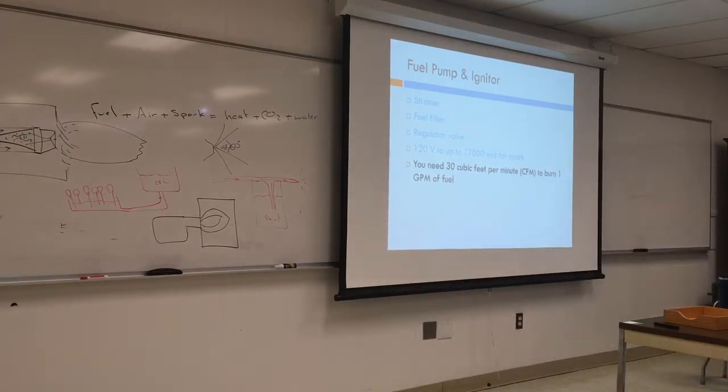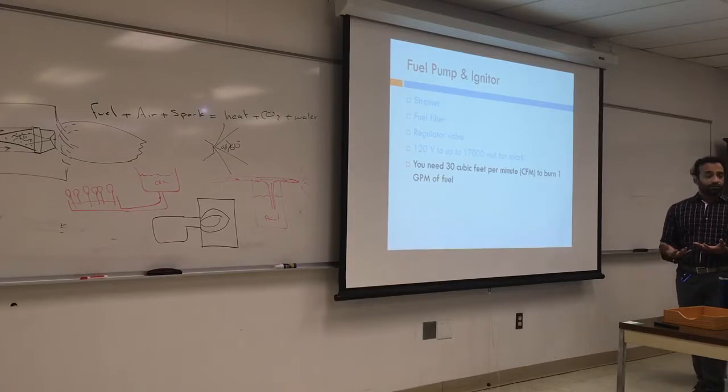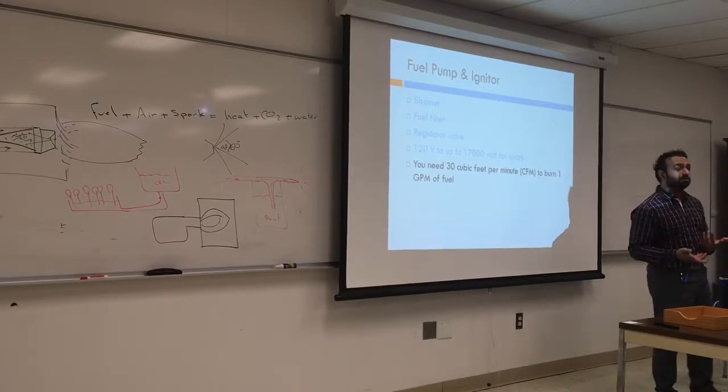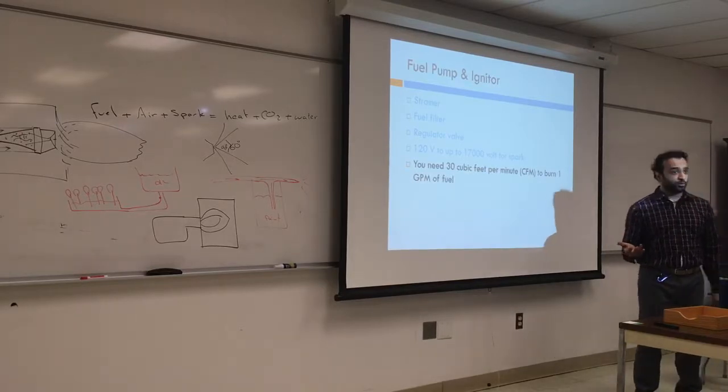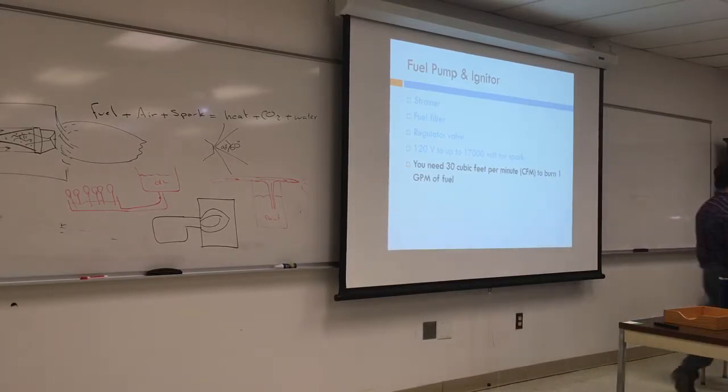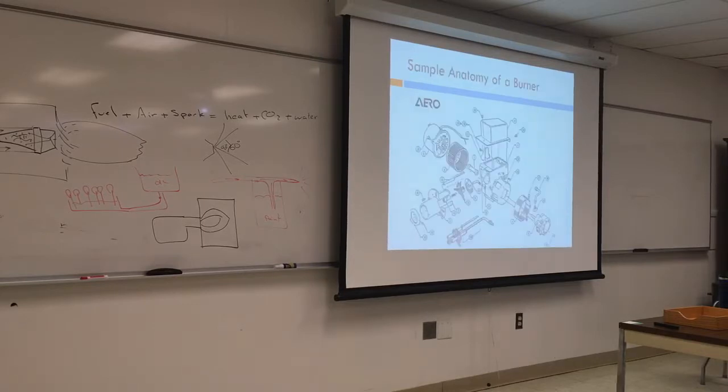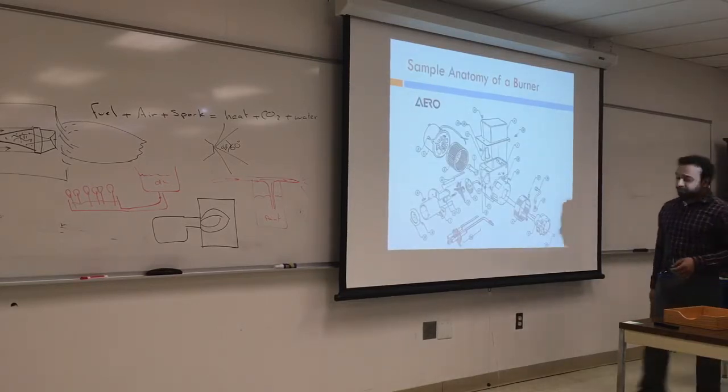And we will see a case where somebody has a ventilation fan that is sucking air outside the house, and that is creating a vacuum inside the basement. By doing so, you don't have enough air inside that chamber. And if you don't have enough air, you'll have what? Smoke. That could be one of the reasons. You have smoke, the cad cell might be covered with smoke, and you will have delayed ignition or even more heat.